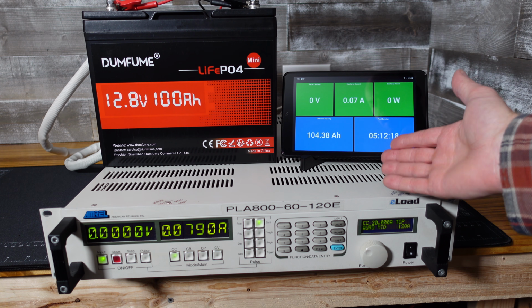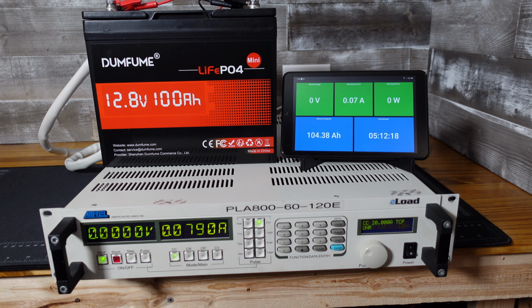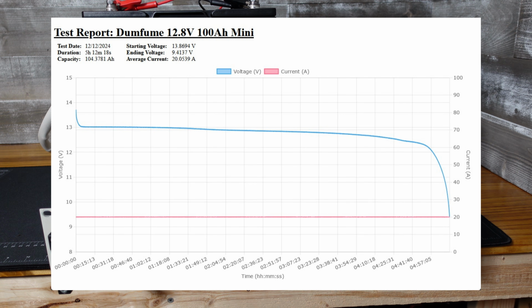104.3 amp hours. That is much better than I was expecting, I'll be honest. Taking a look at the discharge report, we started at 13.86 volts, ended at 9.41 volts. The total capacity was 104.37 amp hours, and the test took 5 hours, 12 minutes, and 18 seconds.